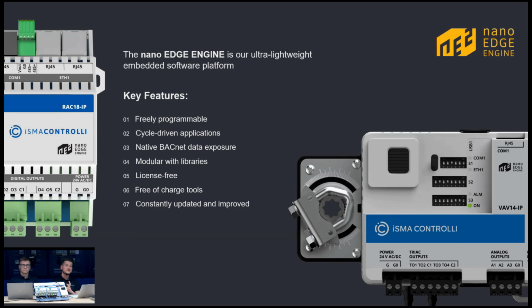Those can be different time cycles for different kinds of applications, even on the same controller. That means RAC18-IP can work as an HVAC controller with an application that has a cycle like 10 seconds. And at the same time, the controller can work with a lighting application with the time cycle going down to, I believe it's 100 milliseconds, right? So this controller is extremely fast.